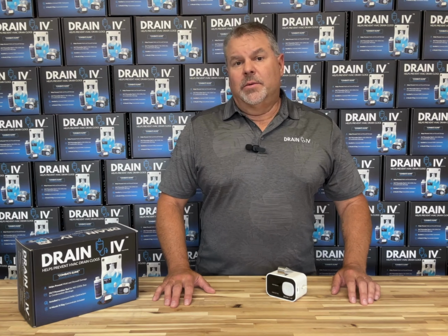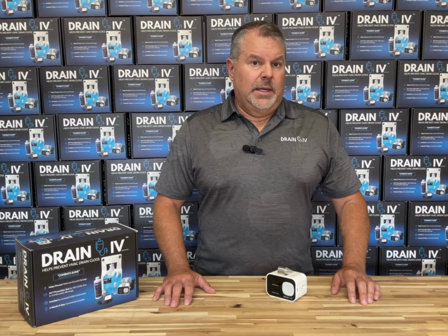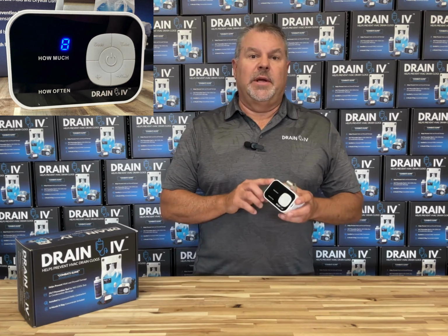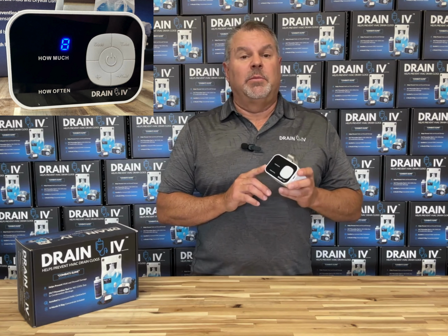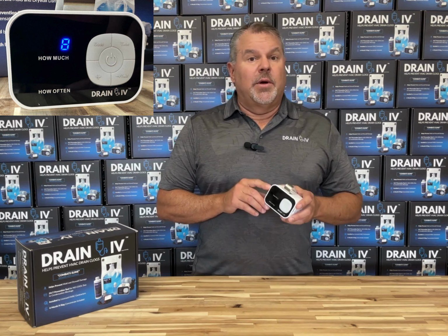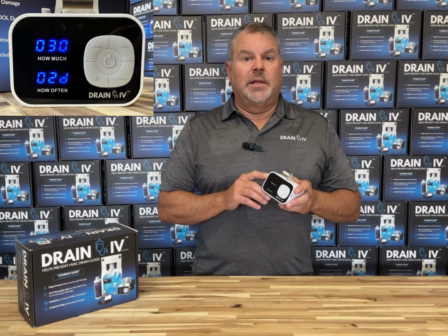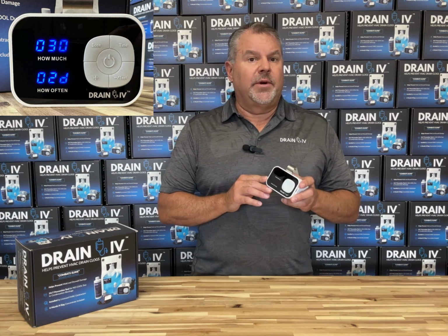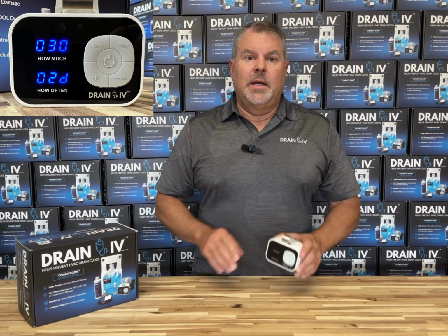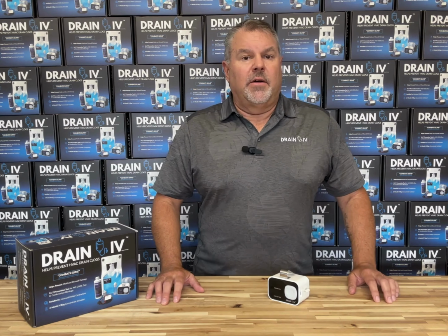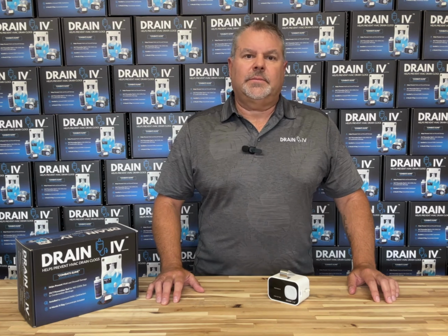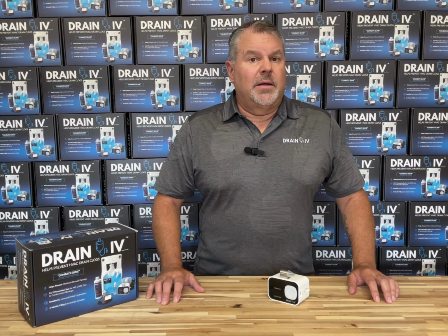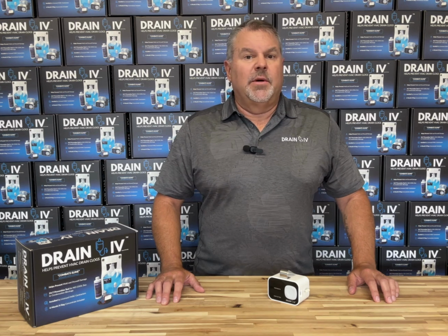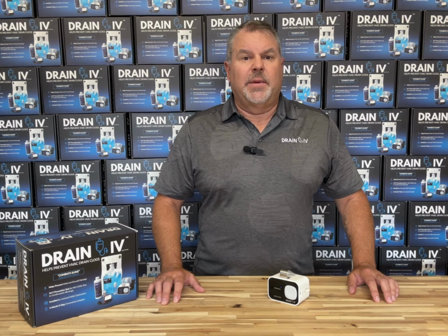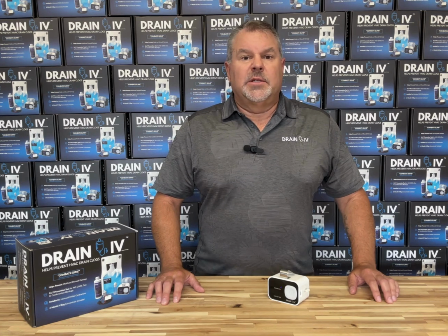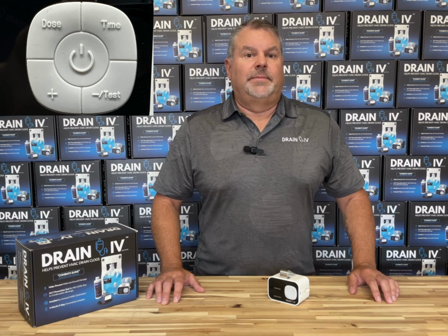The display has two modes, sleep mode and awake mode. In sleep mode, how much will display the battery level and how often will be blank. In awake mode, how much will display the dose amount in milliliters and how often will display the time frequency of the dose in days. Please note that when the pump is powered off, only sleep mode is available. When the pump is powered on, both modes are available and sleep mode is the default 20 seconds after the last button is pressed. To wake up the display, single press the power button.